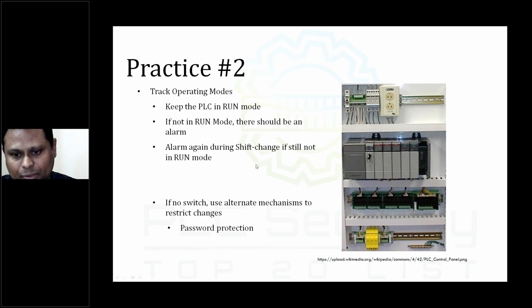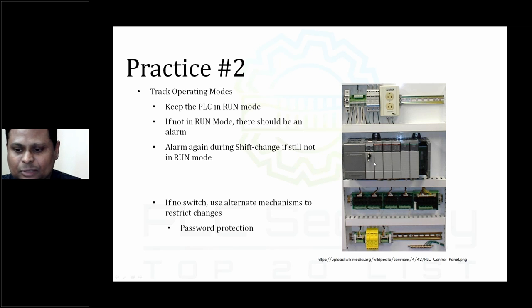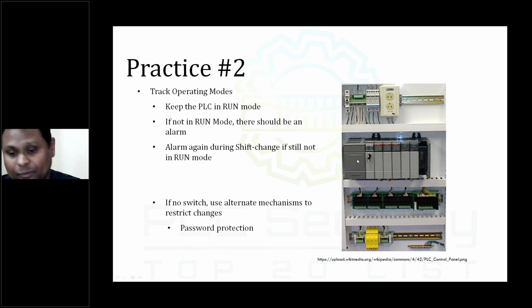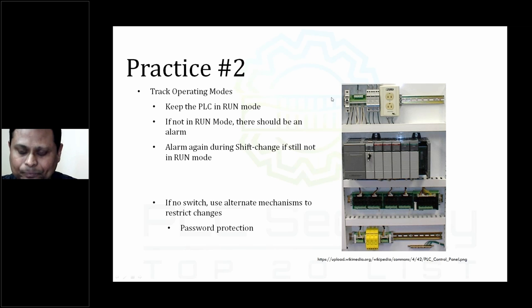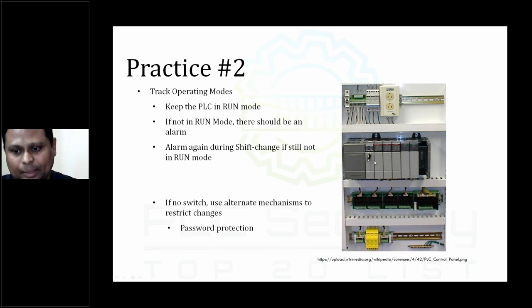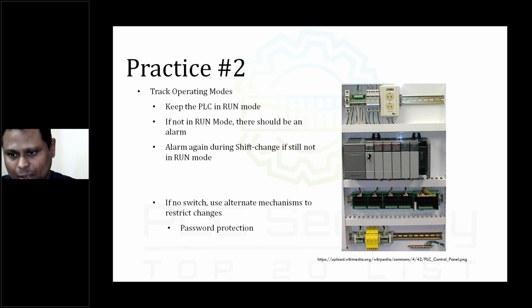At the end of a shift, make sure the alarm pops up so that if someone was working on the PLC, the operator would know, acknowledge it, and close the permit — then the PLC can return to Run mode. PLCs are often left in Remote mode because the engineer might need to reach a hazardous area, or call a buddy operator to switch modes remotely. But the key is that a malicious attacker doesn't have a buddy operator and doesn't have physical access to the PLC.